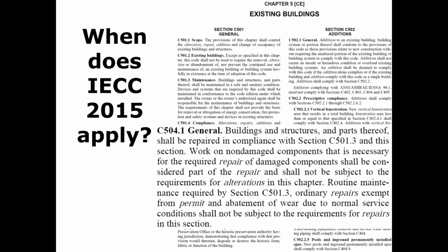Only the thing you're changing has to comply. So, for example, when we change out a rooftop unit, the rooftop and its related components have to comply, but it doesn't mean we have to go change out the boiler or something else like that, right? So we take off the rooftop efficiency and its associated attached accessories like economizers and things like that are going to have to be updated with that. So basically whatever you touch has to comply.